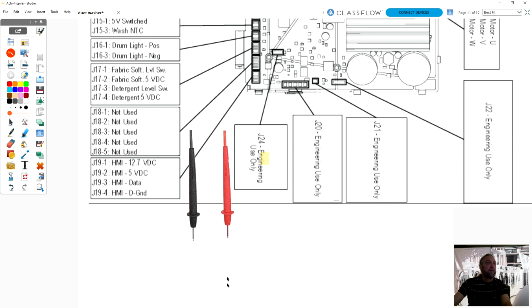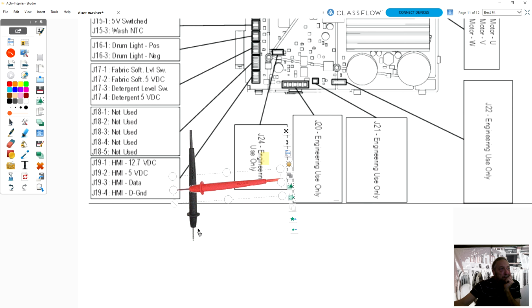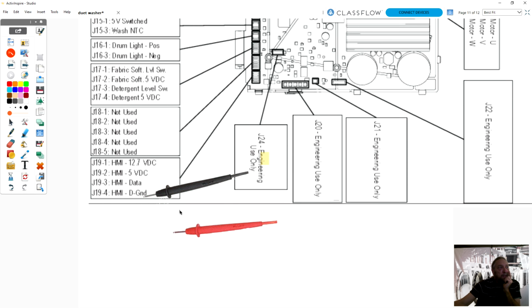Alright, so where would I put my red and black meter lead, and what am I testing for? I would put the black to J19.1 and then go back down and put my red to J19.4 to see if I get the reading from that. If that's good, then I will put my black on J19.2, but leave my red at J19.4 to see if anything is missing from there.